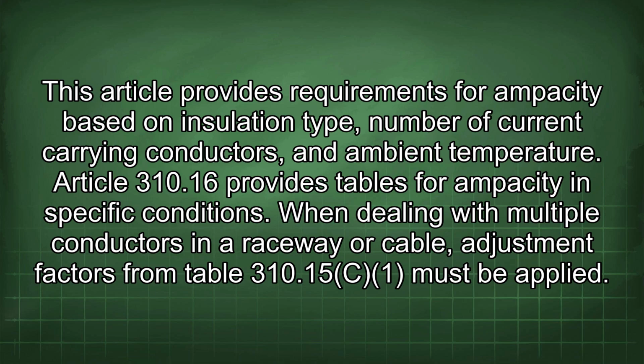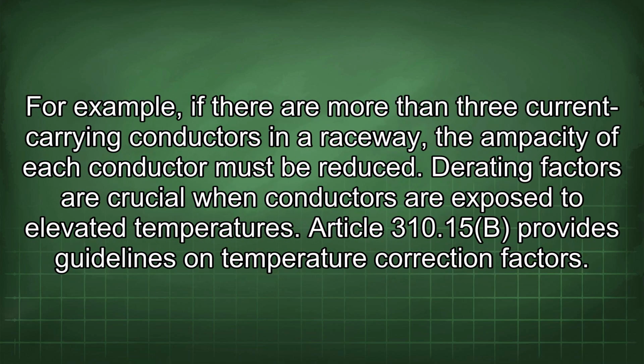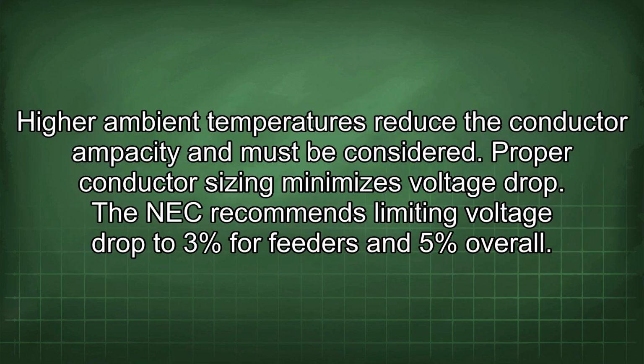When dealing with multiple conductors in a raceway or cable, adjustment factors from Table 310.15 must be applied. For example, if there are more than 3 current carrying conductors in a raceway, the ampacity of each conductor must be reduced. Derating factors are crucial when conductors are exposed to elevated temperatures. Article 310.15(B) provides guidelines on temperature correction factors. Higher ambient temperatures reduce the conductor ampacity and must be considered.